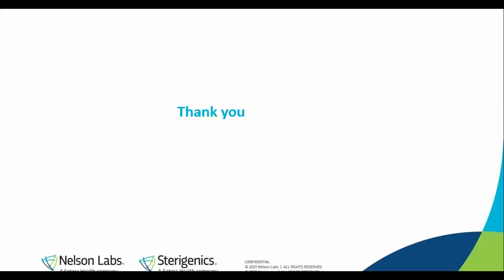The bottom line is that you still have to comply with all the sections of the ISO 11135 standard to be able to show evidence that you have a validated process. Keep in mind that you had a validated process in the beginning. You're going to be changing parameters to optimize them. So in essence, you have a different process. So you'll have to go through 11135 and show evidence that you're complying with all the important sections, such as process definition in Section 8, and obviously the MPQ and PPQ validation that Russ talked about in Section 9. Great question.